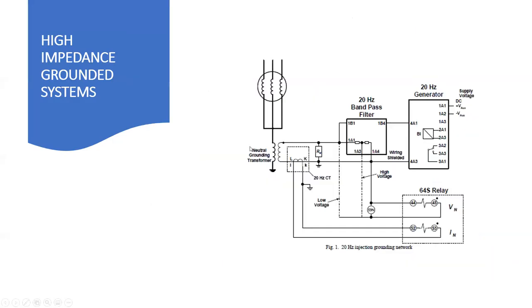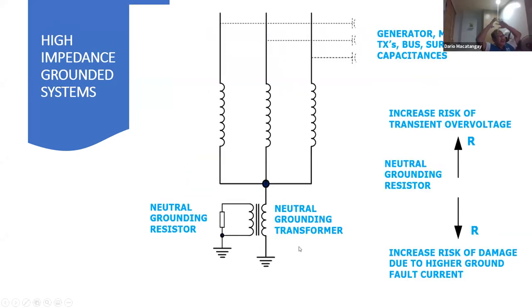All right, so here. This relay will actually, when it reaches the peak of voltage, trip the relay across because of the fault here, right? Now, when you size this grounding resistor, we have to balance two things, because if you increase the resistor, the risk of transient overvoltage is more. What I mean by transient overvoltage is that if you have a fault on one phase, the healthy phases will increase because of the presence of these capacitances. Now, usually you size this resistor to about 1/3 of the overall capacitances of all of this.